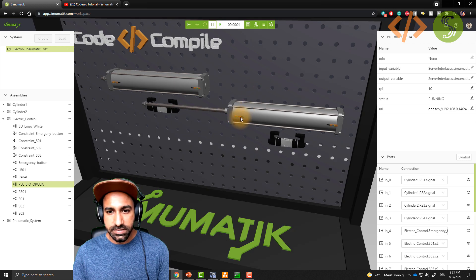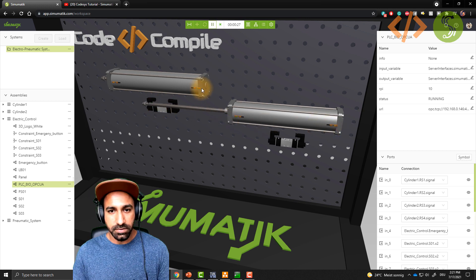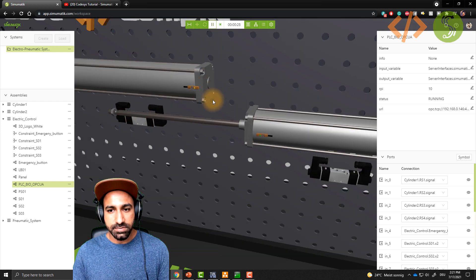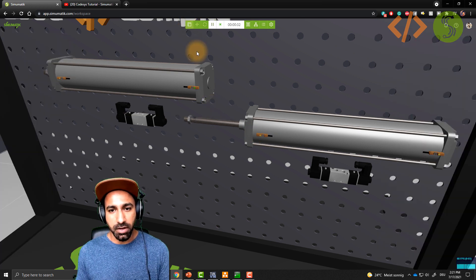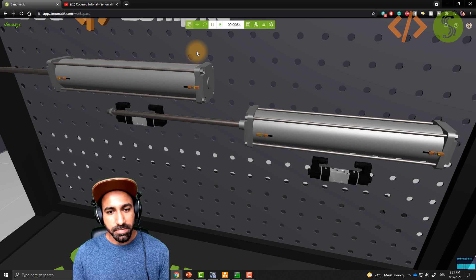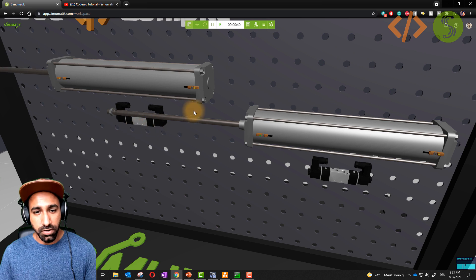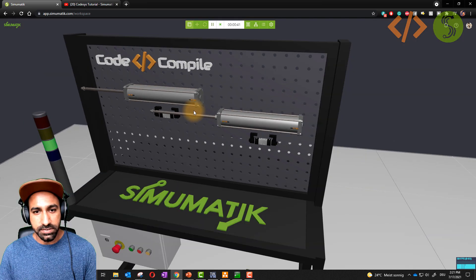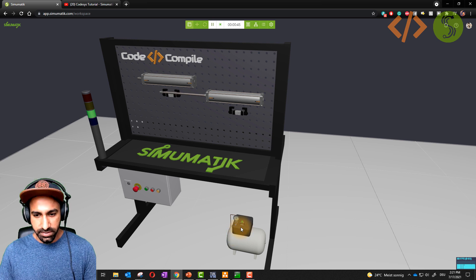These reed switches give feedback on whether the cylinder is fully extended or fully retracted. The reed switches are used to give position feedback to the PLC. Based on that we will make a logic, and these cylinders are energized by direction control valves — five by three valves — energized using an air compressor at the bottom. You can also see a pressure gauge.